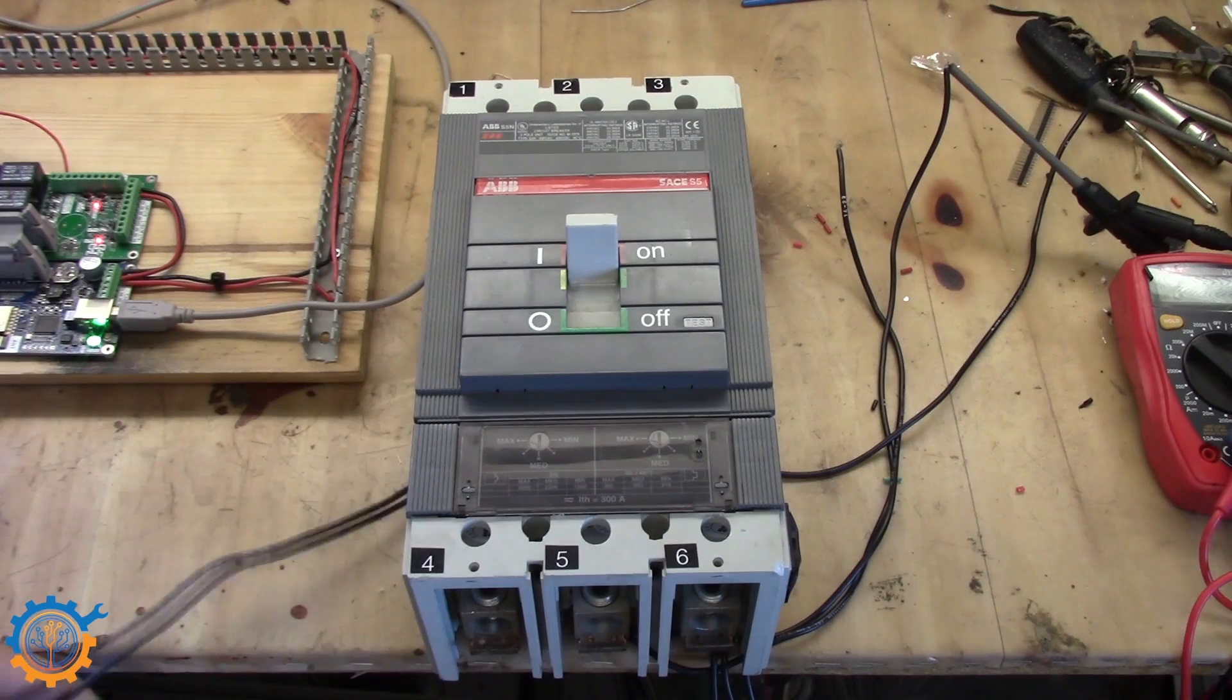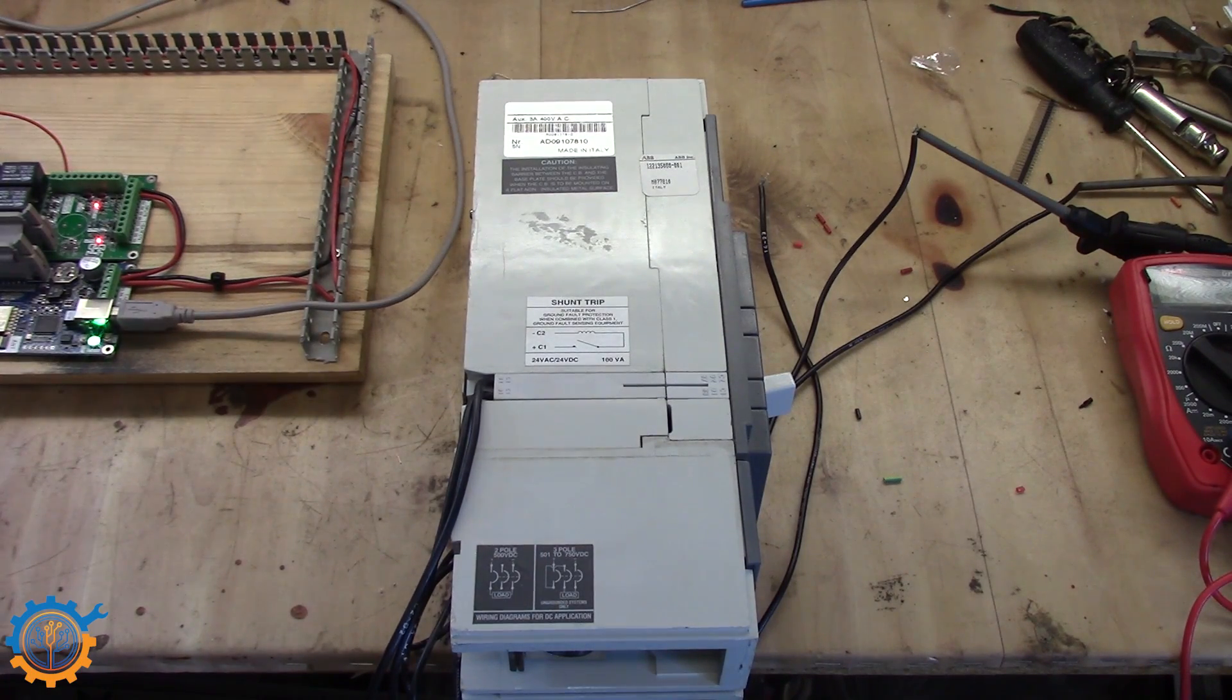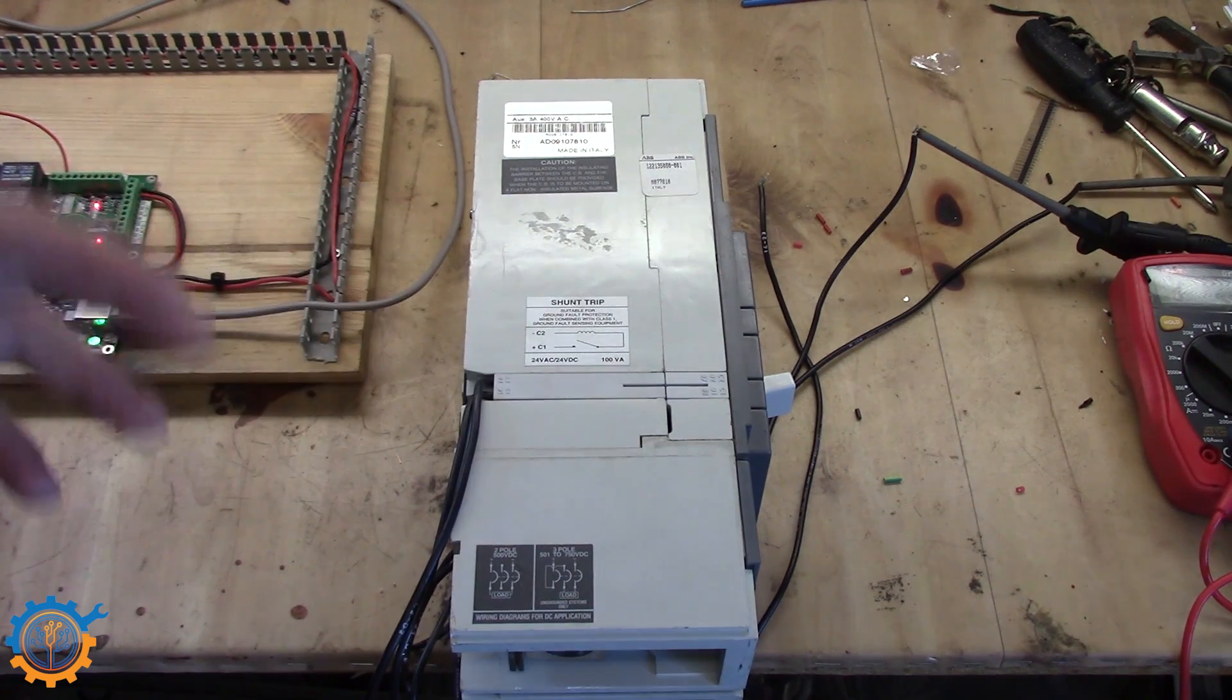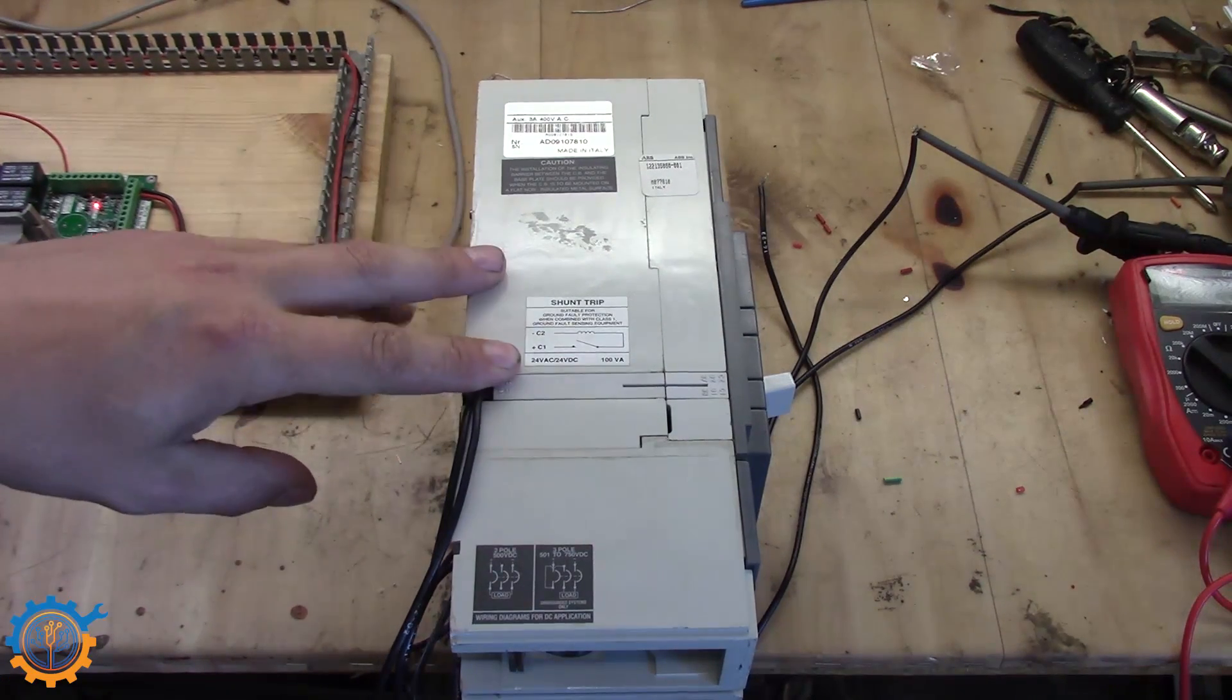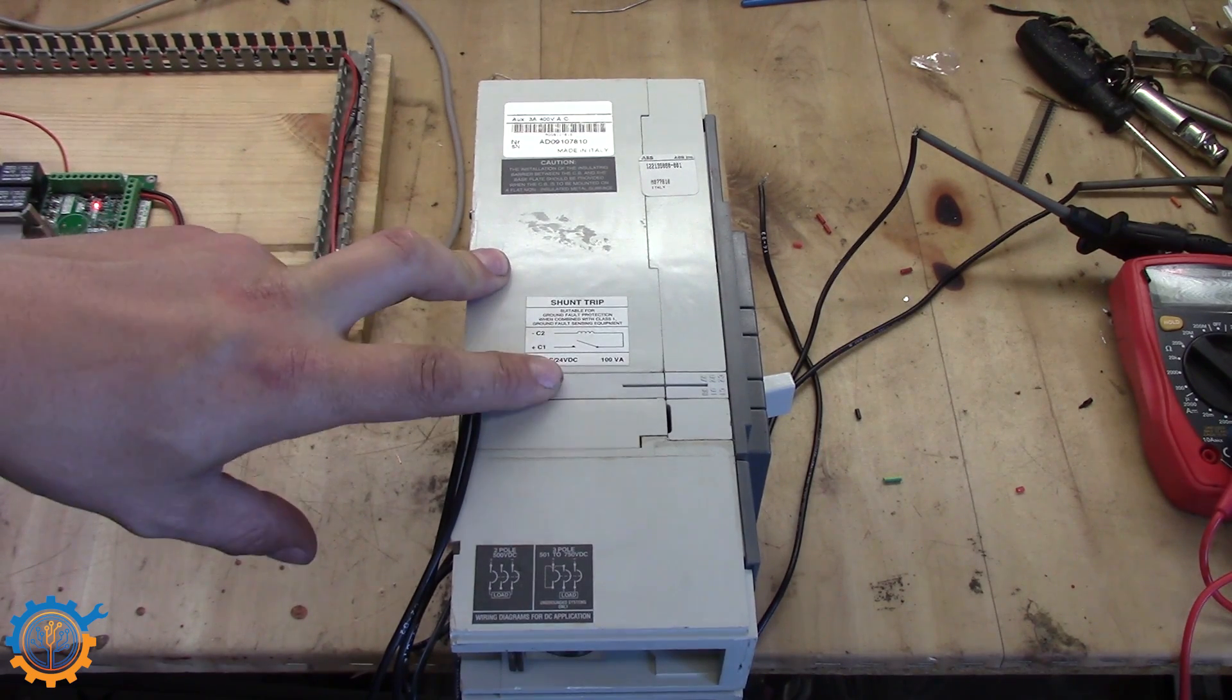I am going to base this video on this huge breaker that I have here. It is 300 amp and it does DC as well. What is important when you get your breaker that you are going to control is the so-called shunt trip. And this is on one of the versions. You can of course use a contactor or anything else like that. The shunt trip here that I have on this device is 24 volt AC or DC.